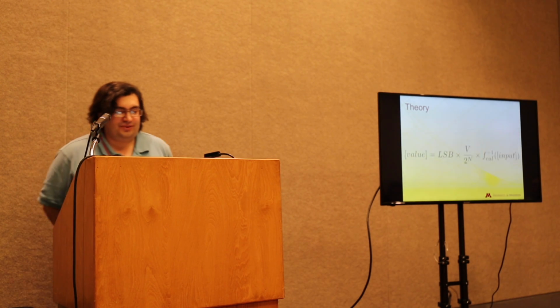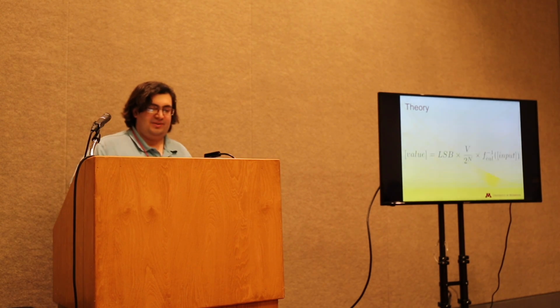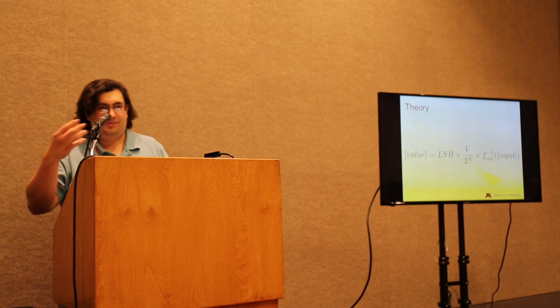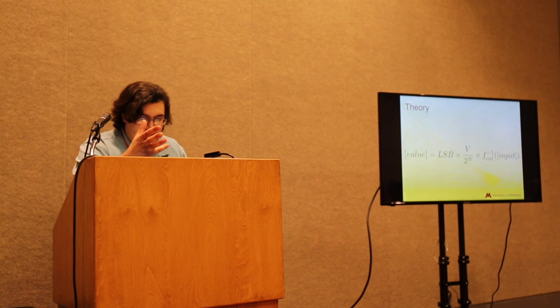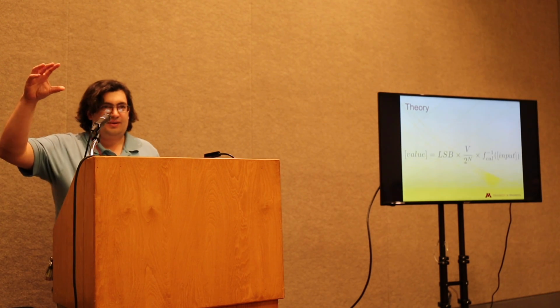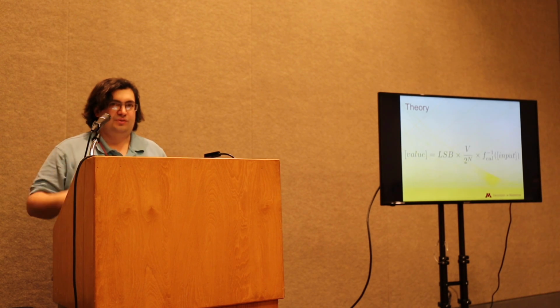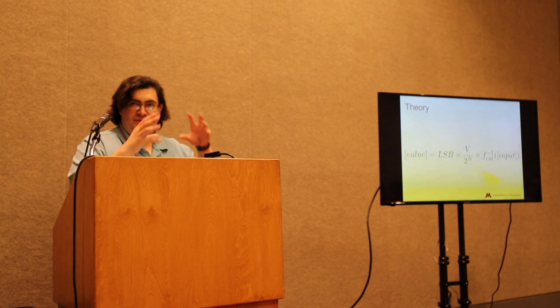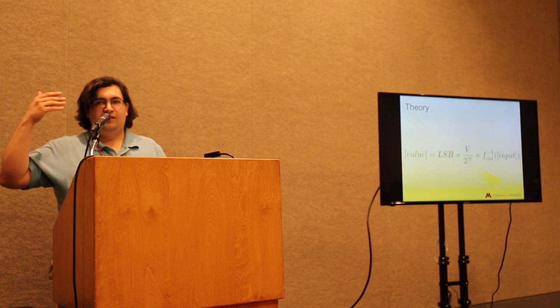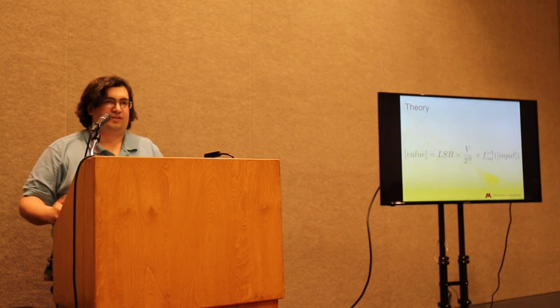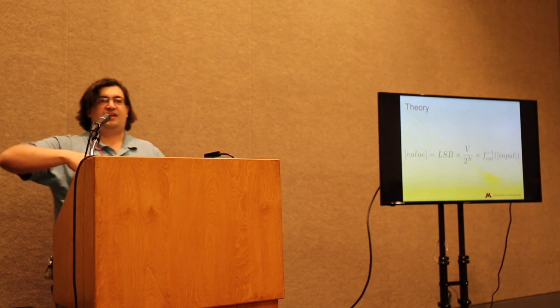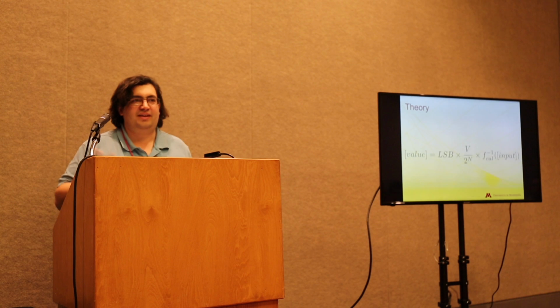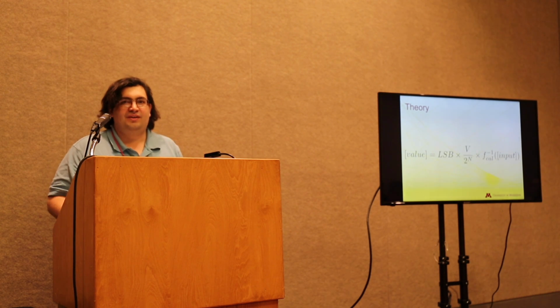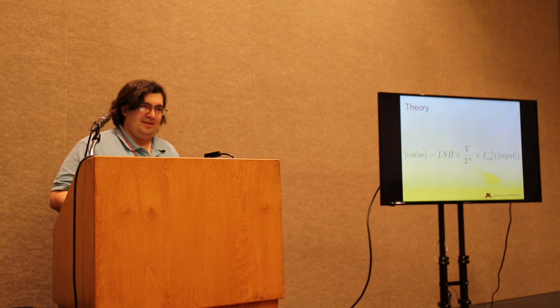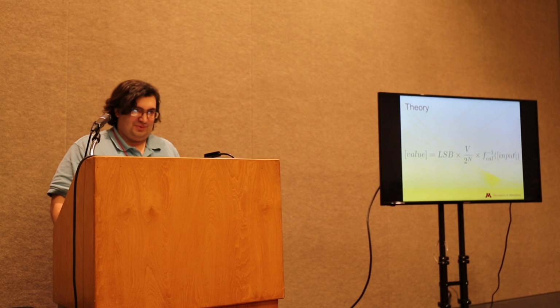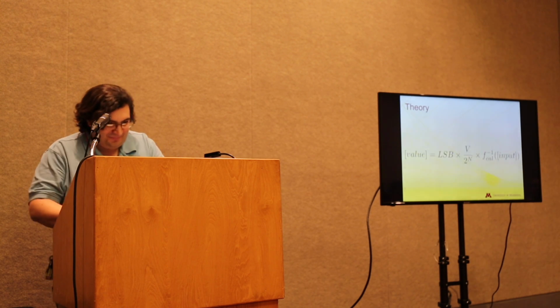So, back to our theory. That means that a value we're trying to measure is equal to a least significant bit count - essentially our binary number - times the voltage that we're checking that against over 2 to the n, where n is the bit depth of your encoding, times some inverse calibration function, something that gives you volts versus, say, meters or pH or something like that, because we're usually measuring in voltage. Unless you're one of those weirdos who happens to measure in current - 4 to 20 milliamp people, I'm looking at you. Sorry.